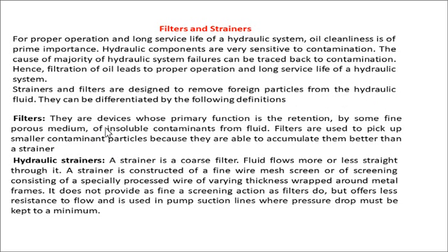Filters are devices whose primary function is the retention, by some fine porous medium, of insoluble contaminants from the fluid. Filters are used to pick up small contaminant particles because they are able to accumulate them better than a strainer. Filters actually retain the impurity, whereas hydraulic strainers are different. These are coarse filters and they don't retain the impurity which they filter out from the fluid.